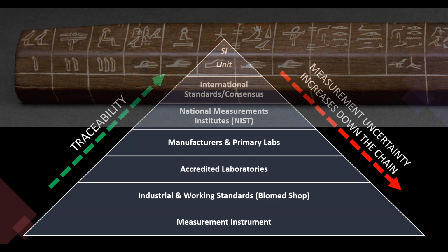So for about $1,650, you've got a really accurate thermometer that can also do 6.5-digit voltage and AC/DC current to 10 amps, high level resistance, and a lot of other functions. But compare that to some of the other handheld PRTs out there that all they do is a 2 decimal PRT measurement at the same price range of $1,650.